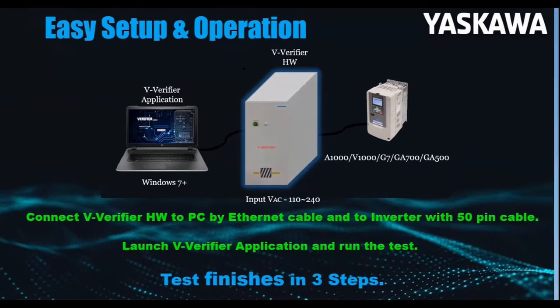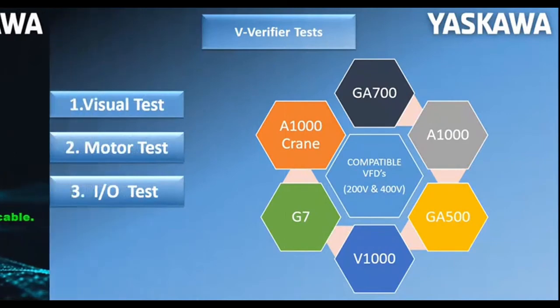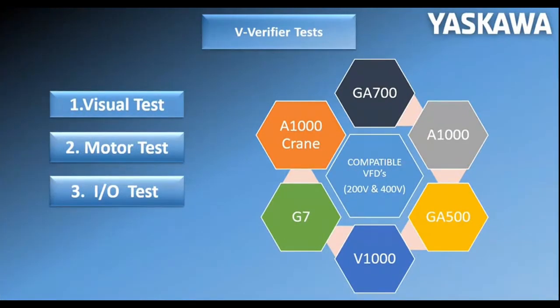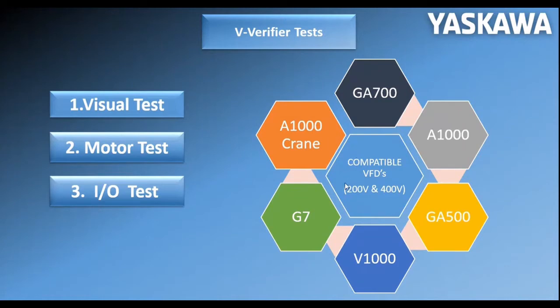The test is categorized into three steps. First, after all connections are made, the UI will execute three steps: visual step, then motor test, and IO test. This tool is compatible for 200-volt class and 400-volt class for all drives, which includes A1000, V1000, GA700, GA500, and also A1000 crane VFDs.